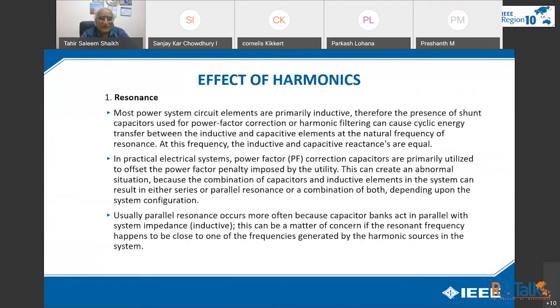Most power system circuit elements are primarily inductive. Therefore, the presence of a shunt capacitor used for power factor correction or harmonic filtering can cause cyclic energy transfer between the inductive and capacitive elements at the natural frequency of resonance. At this frequency, the inductive and capacitive reactances are equal.